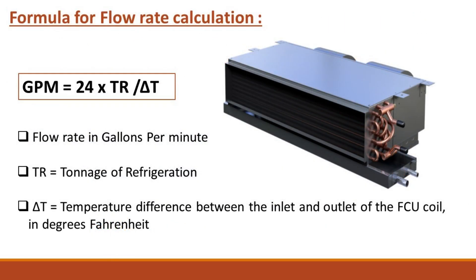First, let's talk about the formula for calculating the chilled water flow rate. The formula is: GPM = 24 × TR / ΔT, where GPM is the flow rate in gallons per minute, TR is the tonnage of refrigeration, and ΔT is the temperature difference between the inlet and outlet of the FCU coil in degrees Fahrenheit.